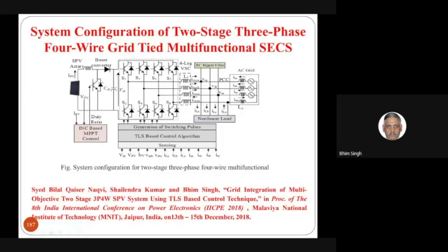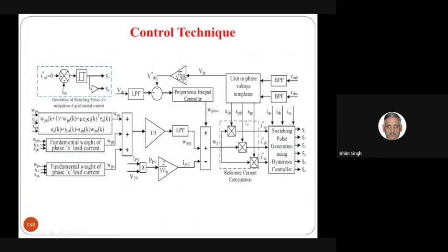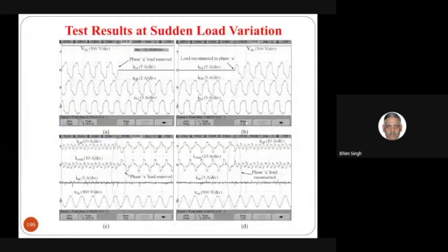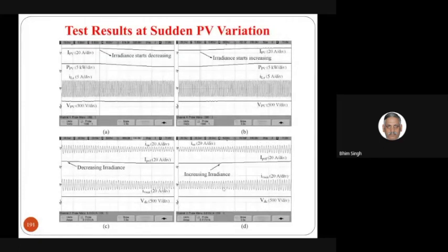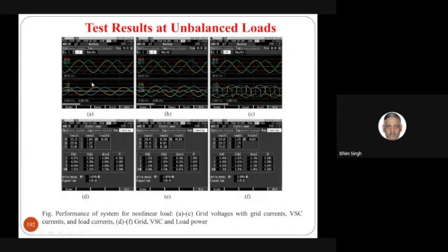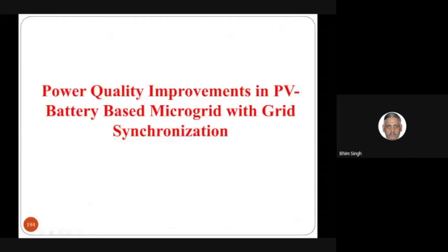The next case is when you have a 4-wire system, typically a 2-stage 4-wire system, considering the neutral current also. The control is modified accordingly with the solar, and you can clearly see one phase load is removed. See how the neutral current behaves, and the grid neutral current is made zero. It compensates for neutral current also, and when the solar insolation reduces or increases, you see how the grid current changes. And you can clearly see how the grid current is balanced when you have the load and the converter current balanced also, and the phasors are there.